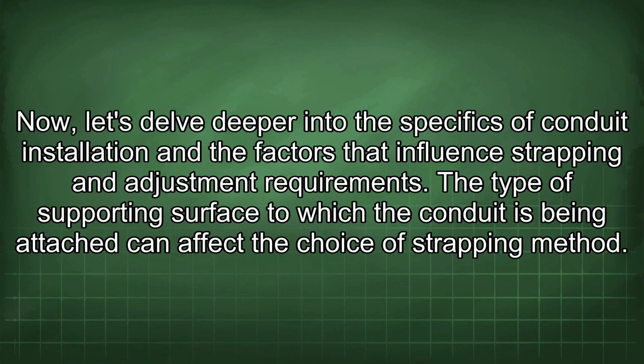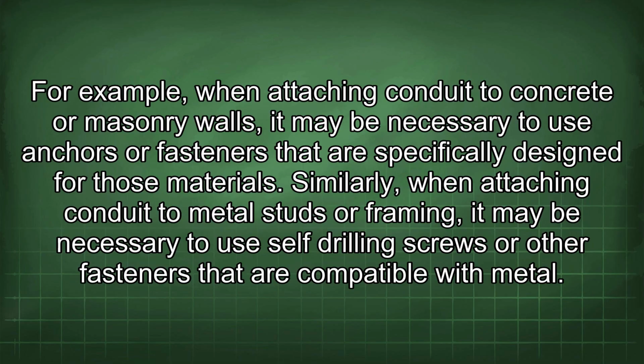The type of supporting surface to which the conduit is being attached can affect the choice of strapping method. For example, when attaching conduit to concrete or masonry walls, it may be necessary to use anchors or fasteners that are specifically designed for those materials. Similarly, when attaching conduit to metal studs or framing, it may be necessary to use self-drilling screws or other fasteners that are compatible with metal.